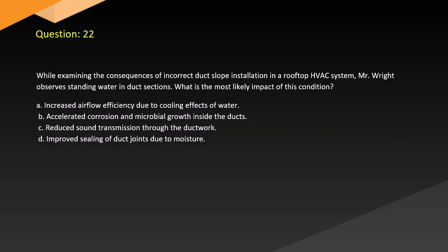Question 22. While examining the consequences of incorrect duct slope installation in a rooftop HVAC system, the inspector observes standing water in duct sections. What is the most likely impact of this condition? A. Increased airflow efficiency due to cooling effects of water. B. Accelerated corrosion and microbial growth inside the ducts. C. Reduced sound transmission through the ductwork. D. Improved sealing of duct joints due to moisture.